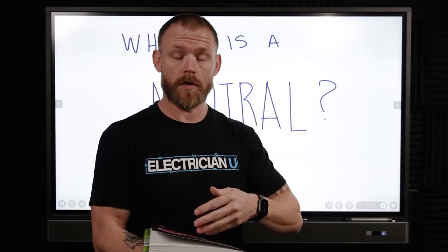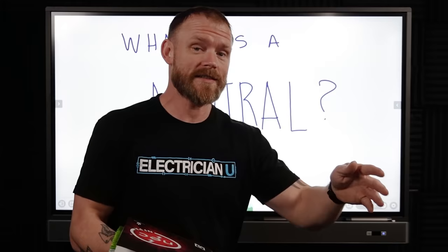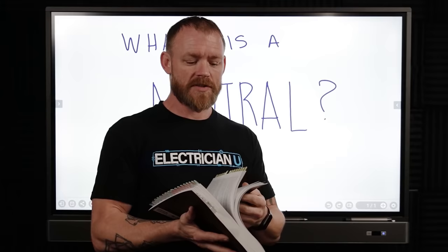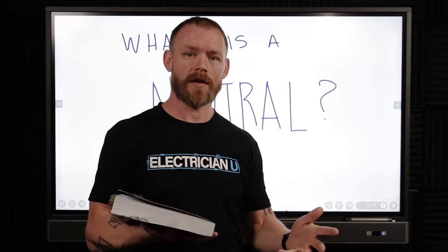There are a couple of different ways that we can look at a neutral. In code, for the longest time, a neutral was just called a grounded conductor. They didn't really go by neutral in most of this book; they called it the grounded conductor, which is confusing because there's an ungrounded conductor and a grounding conductor. So when they talk about grounding, a lot of times as an electrician you think they're talking about the ground, but they're actually talking about the neutral and calling it the grounded conductor.